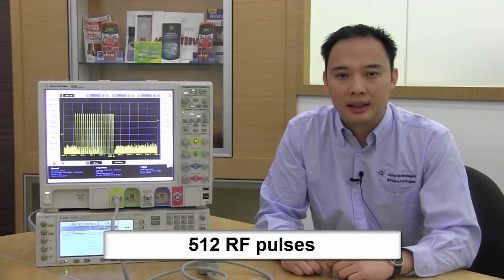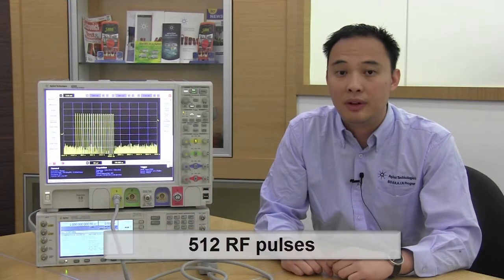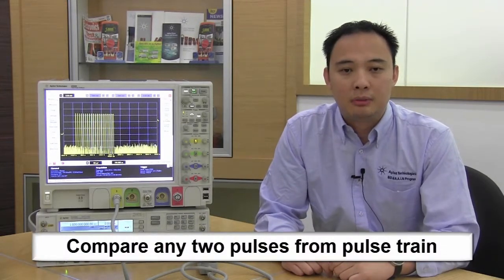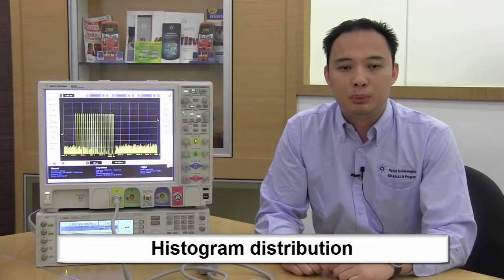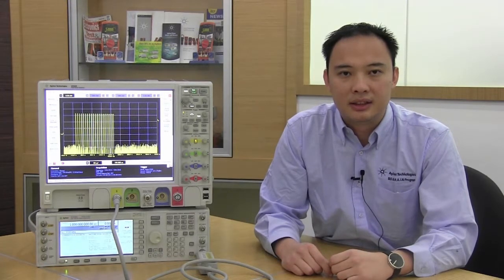The new 8990B multipulse software is designed to first, capture and analyze continuously 512 RF pulses for both RF channels, second, compare any two pulses from the pulse train, and third, display histogram distribution presentation for pulse parameters. These features are especially important for output stability tests.